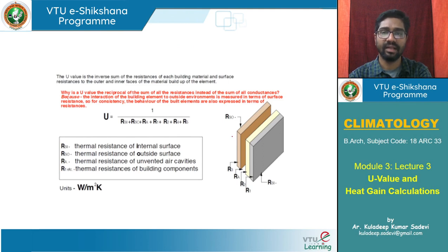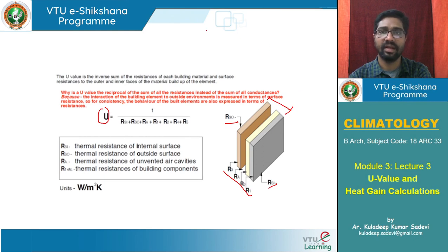We have different materials with different resistance values in different layers. To calculate the U-value of a whole assembly, we must add up resistances. We cannot directly add conductance (U-values). Only resistance is directly additive: R = R1 + R2 + R3 and so on. Once we know total R, we calculate U as 1/R.